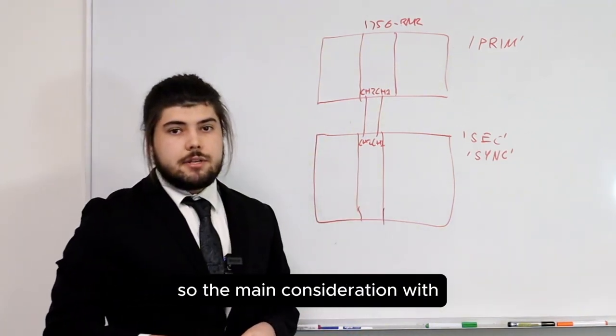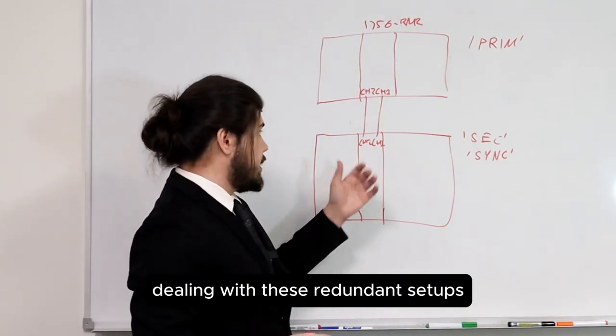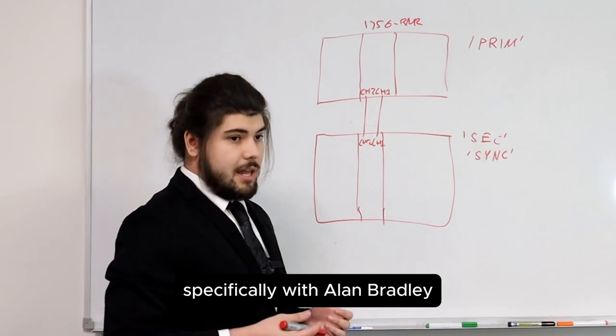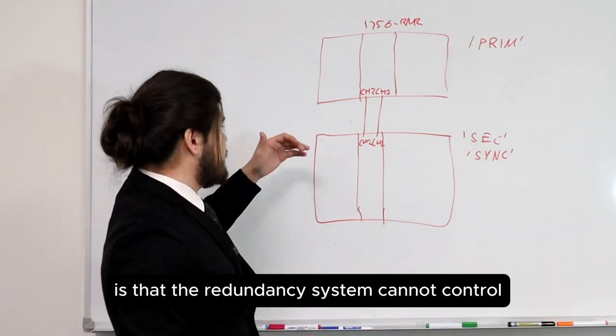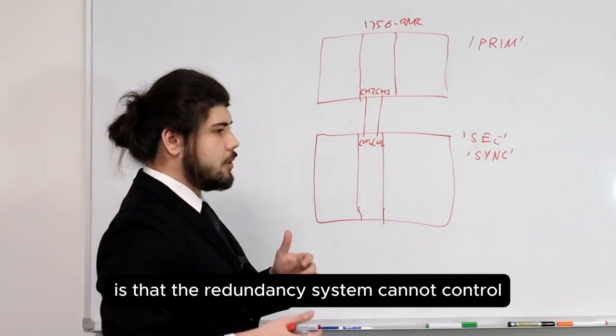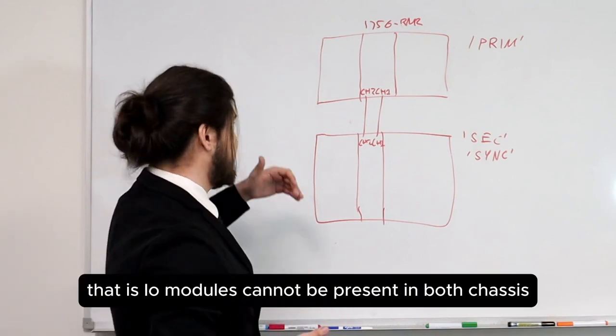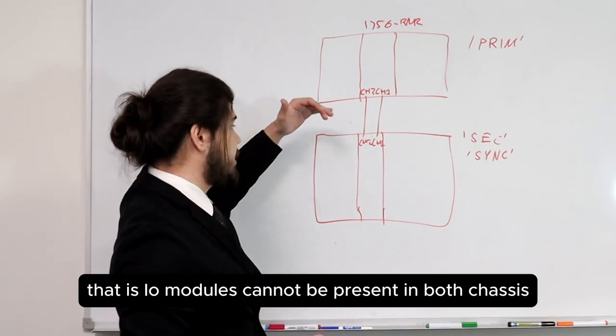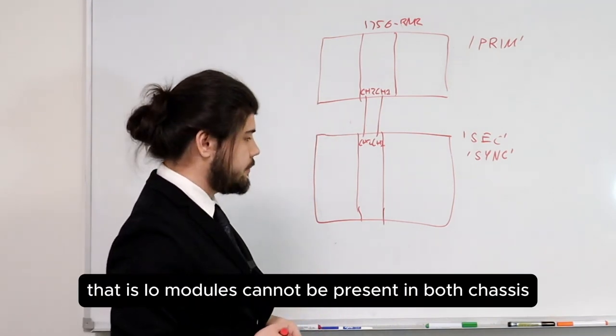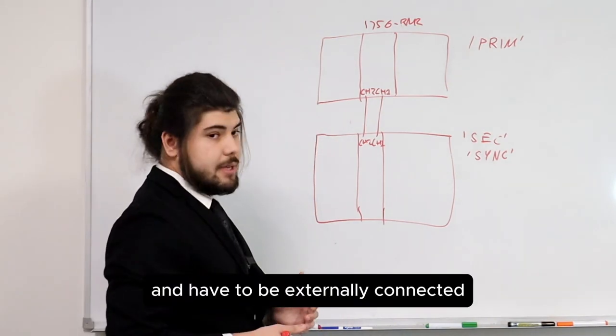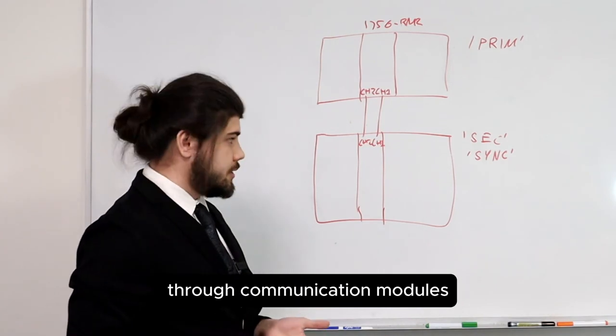The main consideration with these redundant setups, specifically with Allen Bradley, is that the redundancy system cannot control remote IO directly. IO modules cannot be present in both chassis and they have to be externally connected through communication modules.